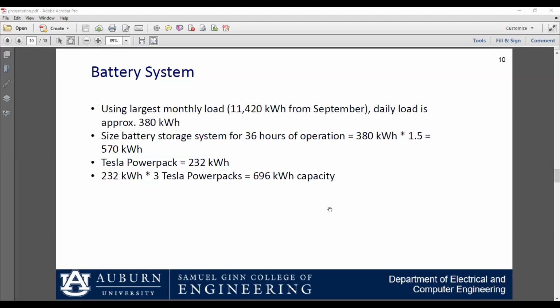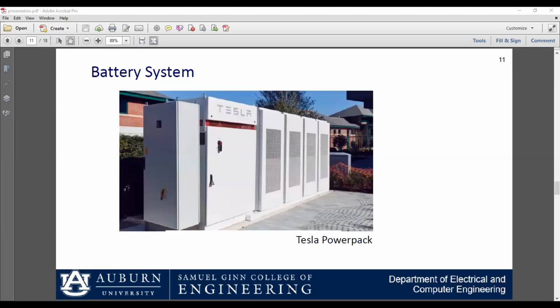There are several off-the-shelf battery storage systems on the market. We looked at the Tesla PowerPack. Each PowerPack is sized at 232 kilowatt hours. And then using 3 of them results in a total capacity of 696 kilowatt hours. So that would provide power for just over 36 hours. It's just a picture of the Tesla PowerPack.